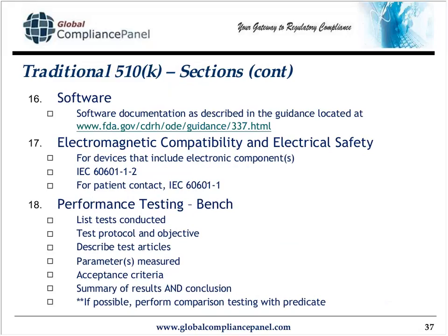Make sure that you have a protocol and also a results document. Also make sure that in your results document, you have a nice little summary of the results and a conclusion. Depending on the nature of your bench testing, your testing may be dozens of pages long. You're going to have to include it, by the way. Therefore, the longer and more in-depth it is, the more appreciative the reviewer is to look at a summary of the results and a conclusion saying that the device is safe and effective.